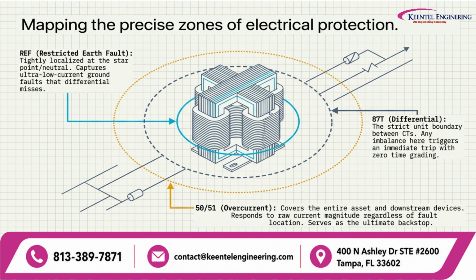Protection zones are fundamental to understanding how transformer protection works. The first zone shown here is restricted earth fault, or REF. REF provides highly localized protection, particularly around the transformer star point and neutral. Its strength is sensitivity. It can detect certain earth faults that may be difficult for broader protection functions to identify. The second major zone is transformer differential protection, or 87T. The differential zone is defined by the CT locations. Current entering and leaving the protected zone is compared, and a significant mismatch indicates an internal fault. Because this is the primary protection zone, the objective is generally zero time, or instantaneous fault isolation, rather than waiting for downstream protection to operate.